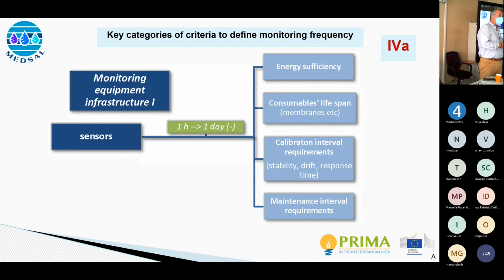Keep in mind that every time sensors - especially ORP, DO, and pH sensors - need to make a measurement, they need to trigger, perform self-checks, take the measurement, then go to hibernation mode and repeat. All these things relate to stability, calibration, and drifting. You need to ensure the overall setup gives an appropriate frequency interval - not overdoing it, but also not losing essential trends in the evolution of the outcome.